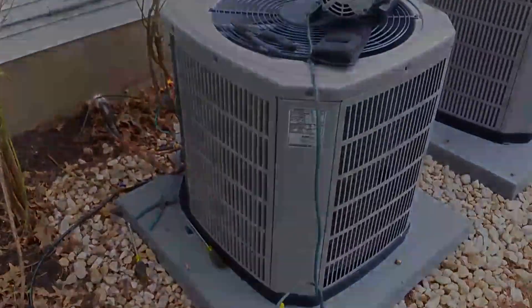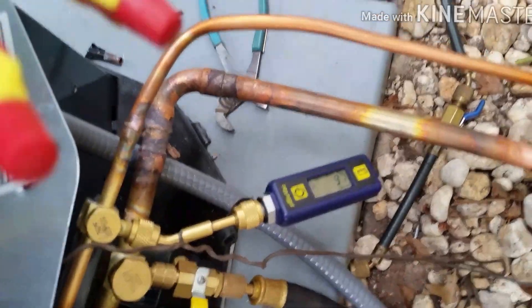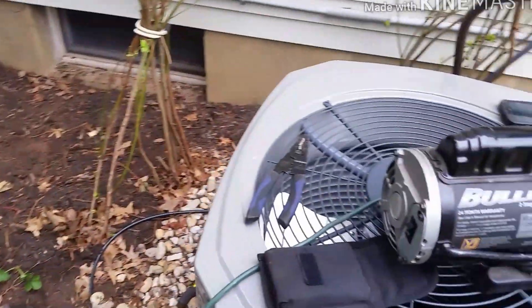At 10 minutes we're at 97 microns — that's good enough in my book. All right guys, I'll check you on the next one. Hope you liked it.